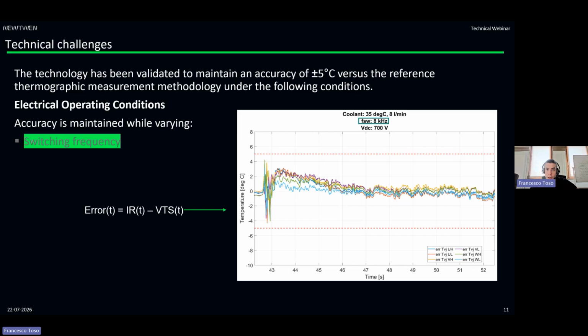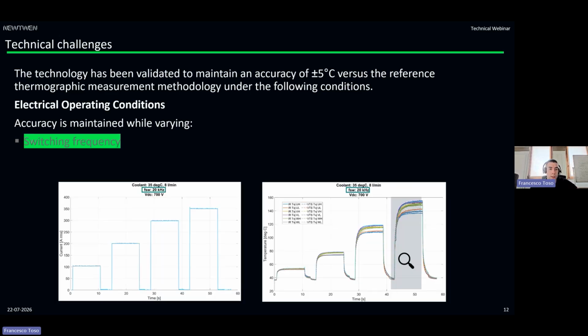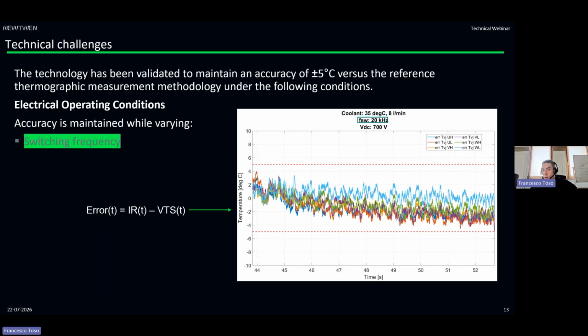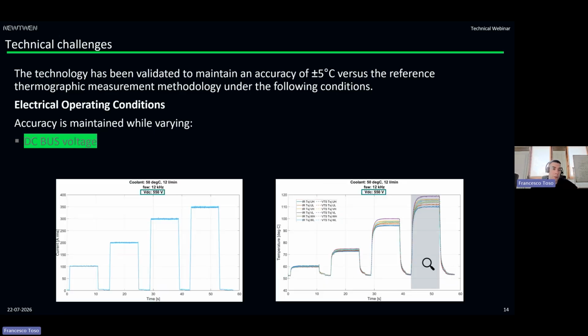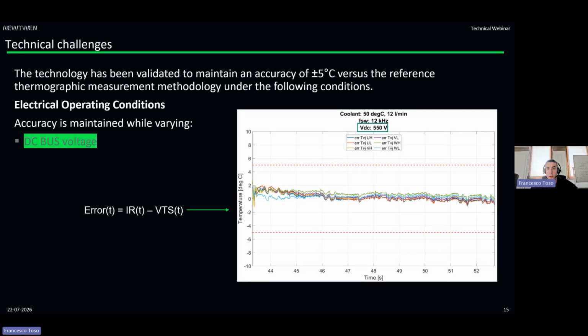Now, if we use the same identical condition, so 35 Celsius degree, 8 liters per minute, 700 volt, and the same identical current profile, but we change the switching frequency from 8 kilohertz to 20 kilohertz, of course, the temperature is much higher, and still the error is within the tolerance. The other electrical parameter that we have to change, because in the inverter itself it can change, is the DC bus voltage. So for instance, in this test, we have 550 volt and a certain thermal step response of the junction temperature with the error within the tolerance.